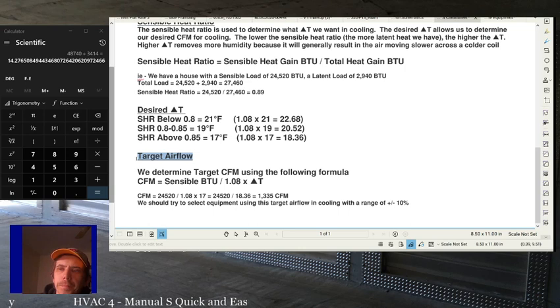On a piece of cooling equipment, we determine it using the sensible heat ratio, and we determine target CFM using the following formula. CFM equals sensible BTUs divided by 1.08 times delta T, which is why I have these cheat numbers up here, right? 1.08 times each of our standard numbers that we would pick.